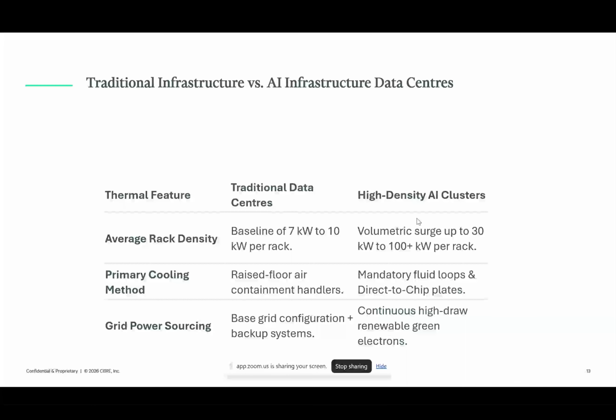Now, what are the key differences when we look at cooling from a thermal perspective? In traditional data centers, we're looking at up to 10 kilowatt per rack, but in AI data centers, which are growing in number, this can go tenfold, up to 100 plus kilowatt per rack. Traditional data centers typically use raised floor containment for cooling, whereas AI data centers use direct-to-chip and mandatory fluid loop. So liquid cooling is a key element of dense AI data centers.